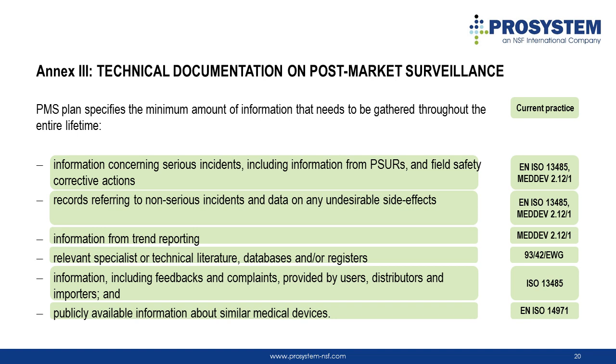The Annex 3 of the MDR sets a requirement for a PMS plan. The PMS plan must describe the process and frequency of activities for gathering post-market data and must cover proactive and systematic procedures to collect any required information. The process shall allow for correct characterization of the performance of the devices and shall also allow a comparison to be made between the device and similar products available on the market.